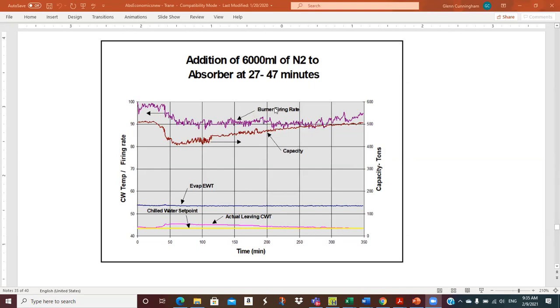And we see the burner firing rate. This is, I think, a direct fired unit, actually goes down because the controls realize that, hey, we've got air in the machine and we've got to back off a little bit. So they actually reduce the firing rate a little bit and hold it constant, just about all the way across this plot. And as you can see, at the same firing rate, capacity starts coming back because the purge is working and the pressure is going down in the evaporator, and we get capacity back on the machine. And then eventually we start increasing firing rate once we get things back to normal, and we eventually pull back down to the chill water set point.